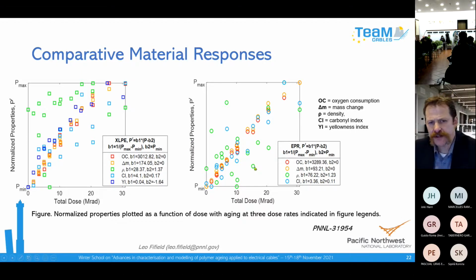So unfortunately, oxygen consumption and mass change are limited to laboratory techniques. It's difficult to measure those for insulation on an installed cable. But this effort showed that those are valuable tools for doing accelerated aging. The understanding is that if we try to do accelerated aging at mild conditions like 90 degrees C, 100 degrees C, where it's going to take many years to come to completion of aging, we can maybe get those early data points and extrapolate the aging from a mild condition in a reasonable amount of time. So that's it for that section.